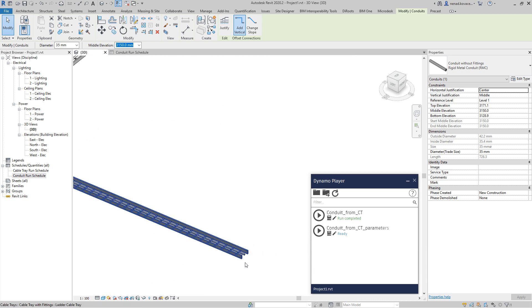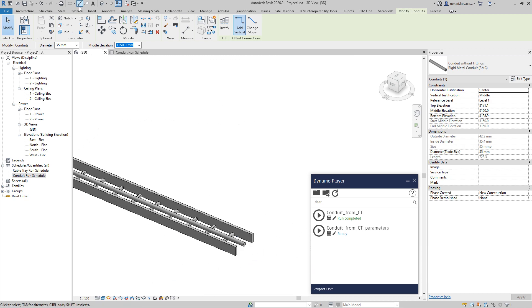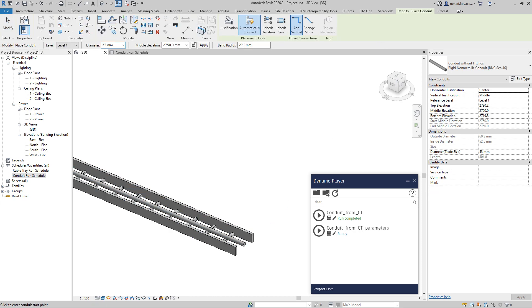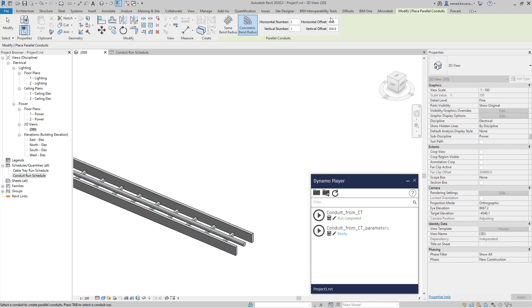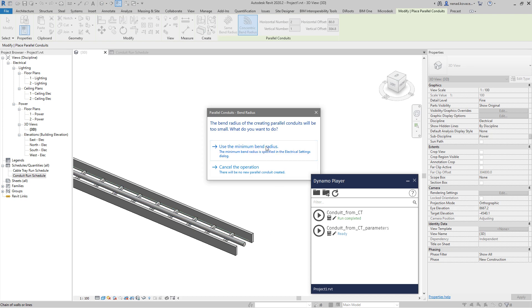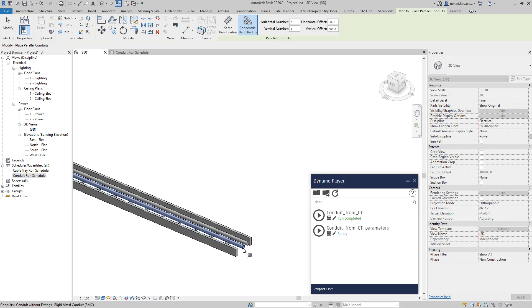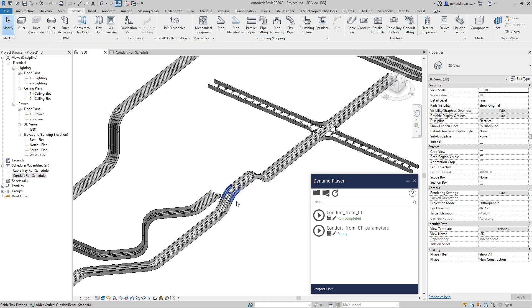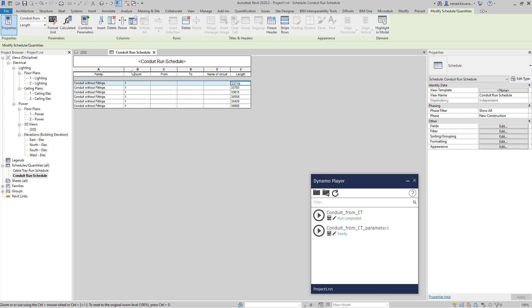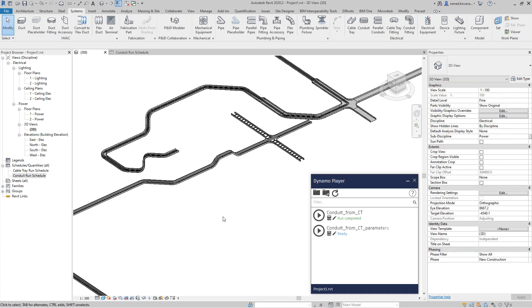Same story — if you need one, two, or even ten more conduits, I'll use the parallel conduit option. I'll increase the offset a little bit — use minimum bend radius — and really quickly we have conduit runs. Let's check: one, two, three, four, five, six — we have six conduit runs. Now if we want to test the second part, I can run the second script.